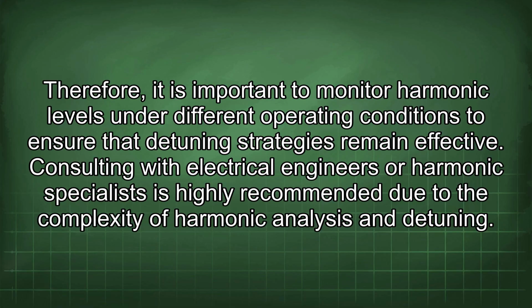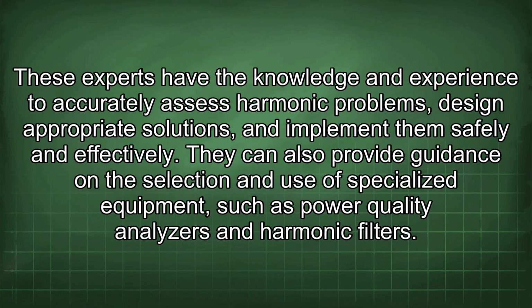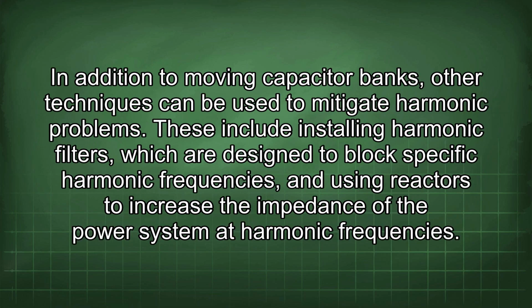remain effective. Consulting with electrical engineers or harmonic specialists is highly recommended due to the complexity of harmonic analysis and detuning. These experts have the knowledge and experience to accurately assess harmonic problems, design appropriate solutions, and implement them safely and effectively. They can also provide guidance on the selection and use of specialized equipment, such as power quality analyzers and harmonic filters. In addition to moving capacitor banks, other techniques can be used to mitigate harmonic problems.